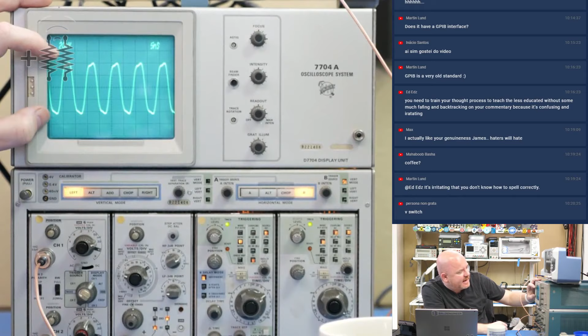So let me grab something I can use to point, and you can see, oh, this will work. So before, we were up to about here where you can't really see it because of my logo. So we're about up to here, and then we came down to about here. So I can see the amplitude is being reduced. And there's a couple of reasons why that's occurring. As we approach the bandwidth limit of this measurement module, we're dropping off some of the high frequency content in the signal, and so that naturally causes the amplitude to reduce.